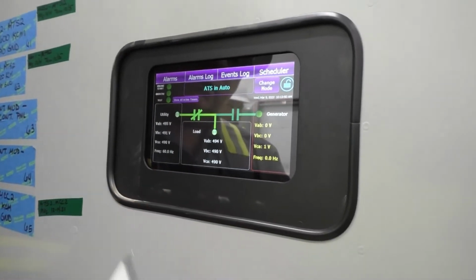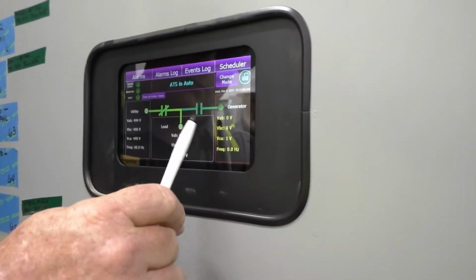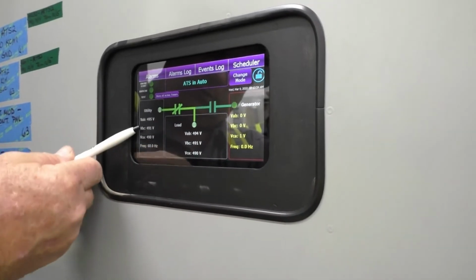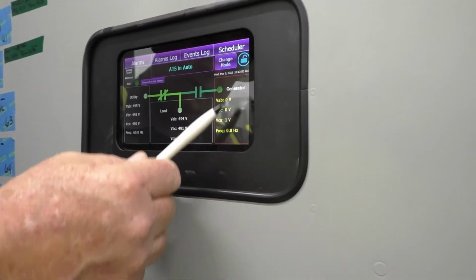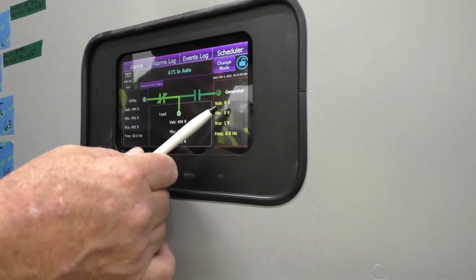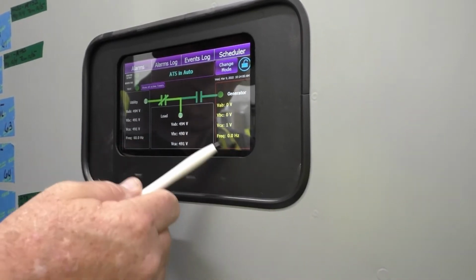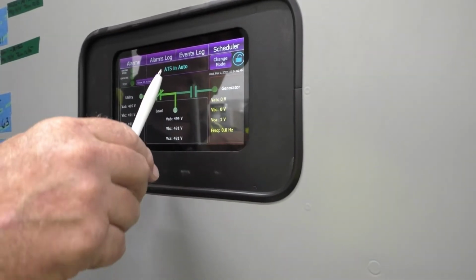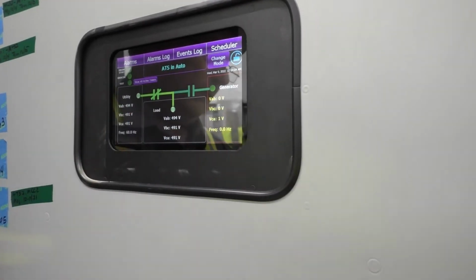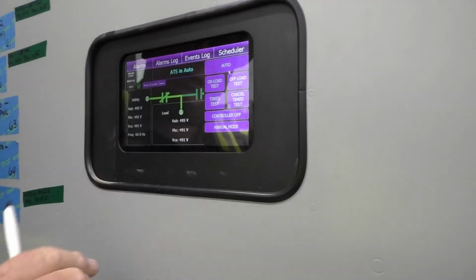Okay, this is the home screen on the transfer switch. When it's green, we have power. I think this turns red, I don't remember off the top of my head, but it tells you the voltage on each phase, the frequency, and so on, and then the load side, of course. Generator's not running, so 0 volts, 0 hertz. ATS is in auto, which means if you have an outage, it's ready. You can take it out of auto. If you hit the change mode button, you can do that.